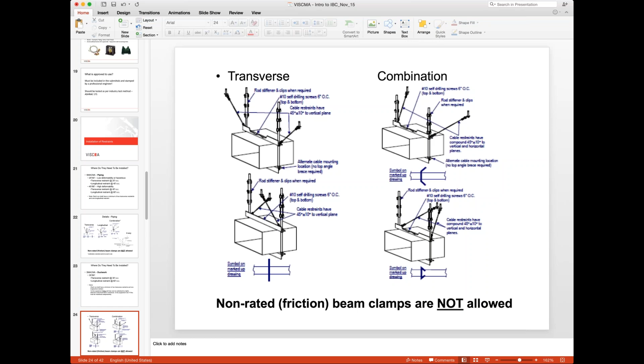All else has to be equal, the same. The math has to be done right. It still has to have the rod stiffeners, and the anchors, as Sammy said, have some kind of third party. He referenced ICC, which generally is the one out there, but there are other third party certifiers for anchors. So to get the allowables from there when you do the math for that one. And it's a very important note at the bottom. Non-rated friction beam clamps are not allowed. The code is explicit that you're not allowed to use friction due to gravity as a seismic restraint.